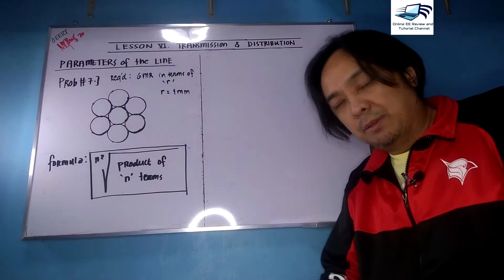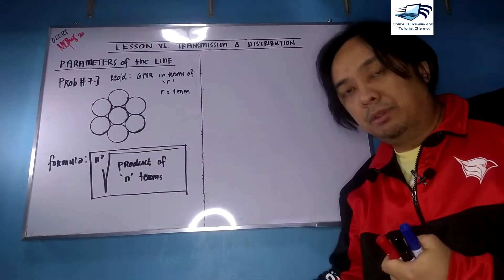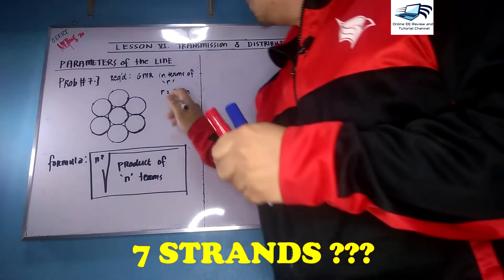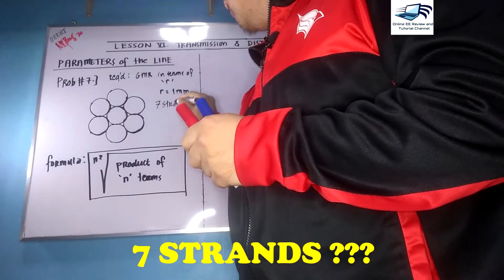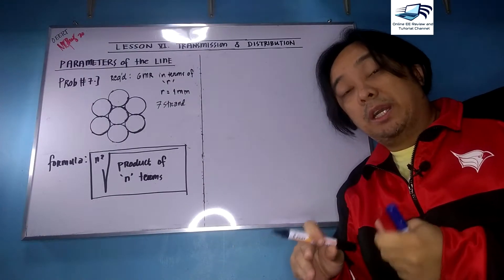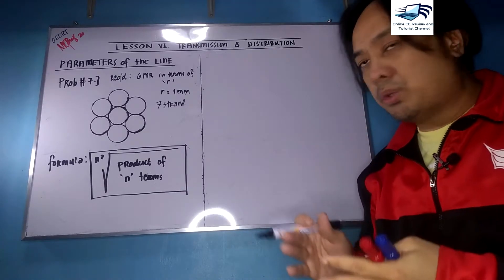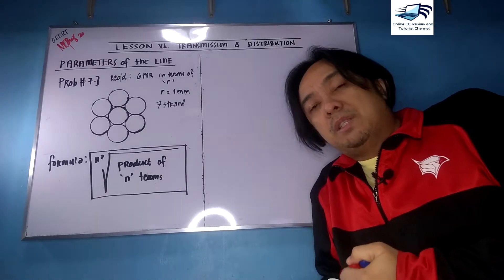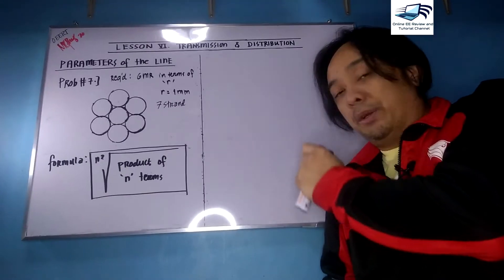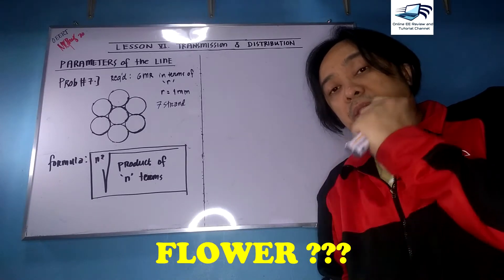To answer this, I have here the figure of that seven-strand conductor. This is a seven-strand configuration and we will assume that each of these conductors are identical. We need to get the Geometric Mean Radius, or DS, or self-distance of this strand or bundle configuration. I usually call this in class as a seven-strand or flower configuration.